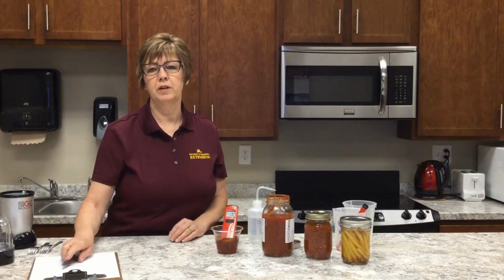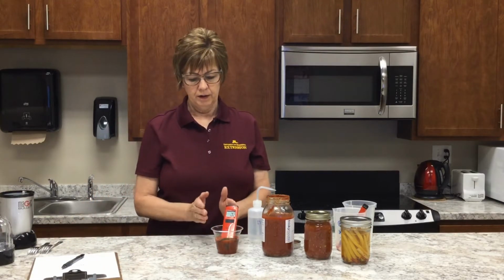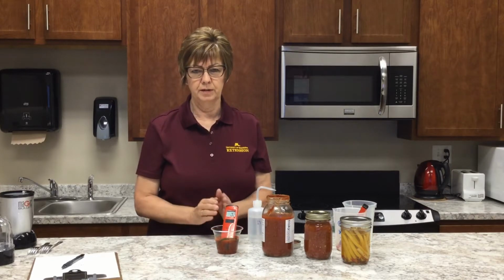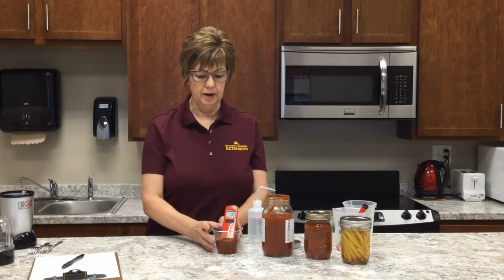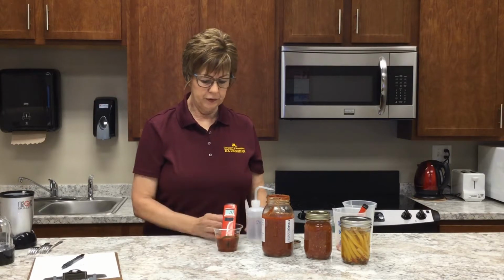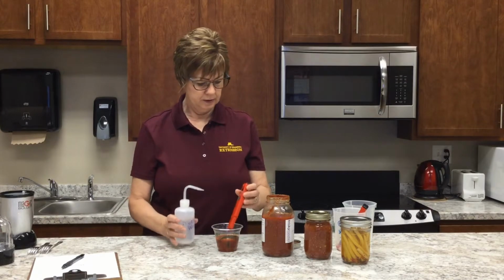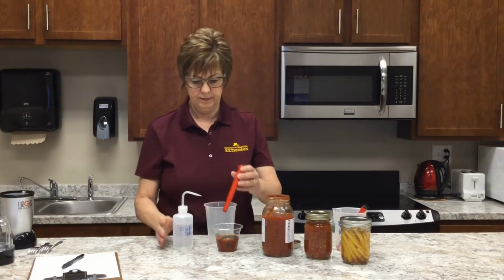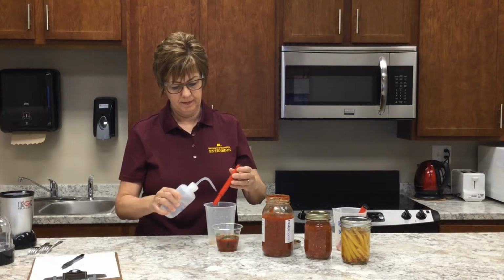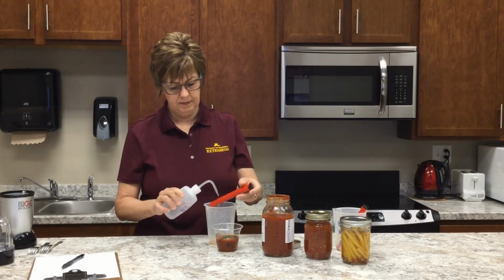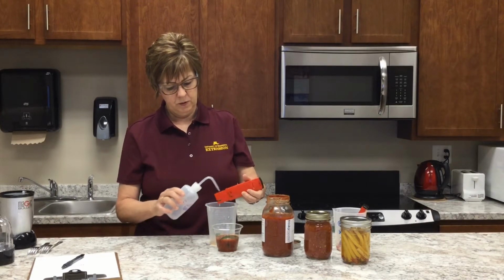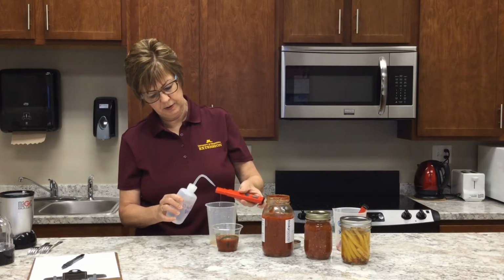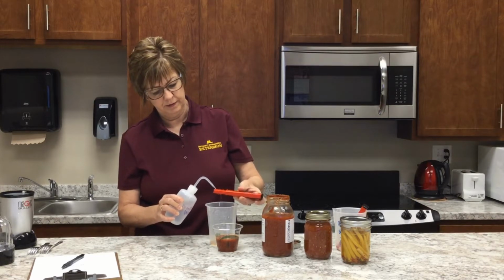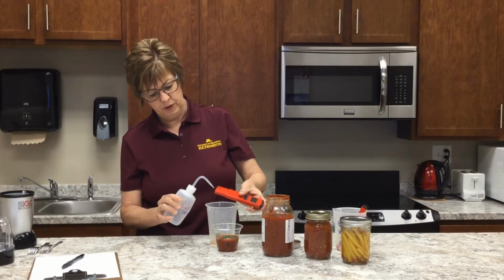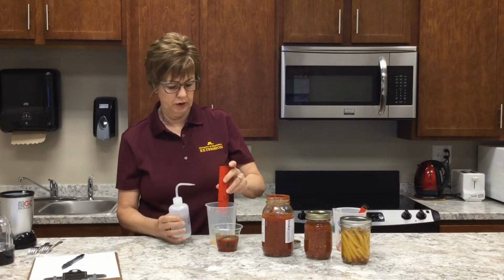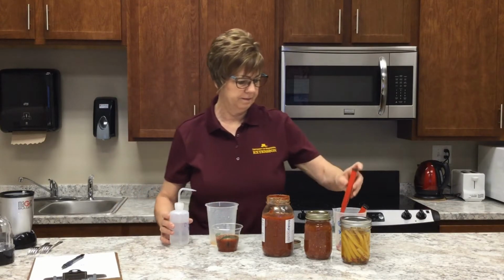Okay, and as I said, we want you to do 2 tests for each batch that you do to make sure your product is testing in that acceptable range. All right, so what we're going to do now is rinse off the meter. And you want to make sure you're getting into the electrodes and so on, as Suzanne had shown us earlier. But we want to get rid of the Bloody Mary mix because we're going to move on and check some salsa.